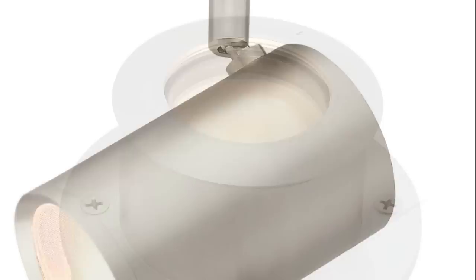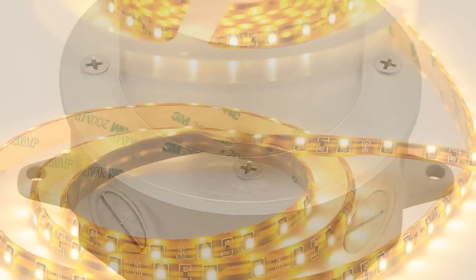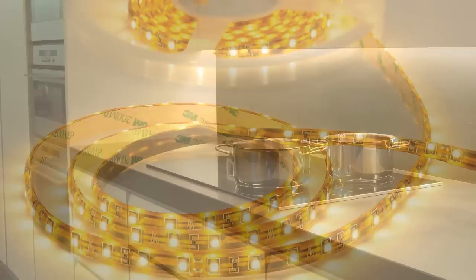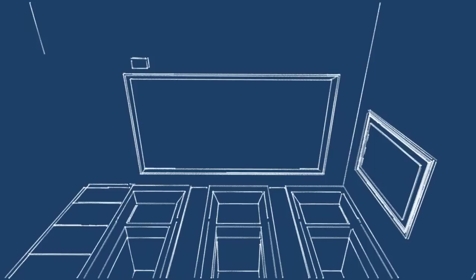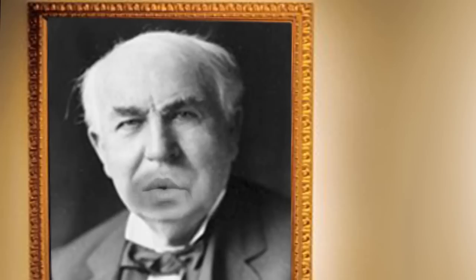Low voltage could mean 12 or 24 volts, whether you're talking about AC or DC. 12 volts makes sense if you're talking about smaller systems, like a soft strip run less than 25 feet, such as under cabinet lighting. But if we have a larger system like cove lighting, we're going to use 24 volts. 24 volts lets us create soft strip runs up to 40 feet with less voltage drop and we can still use the same 14 gauge wire. But what about converting from AC to DC? You can either do that right on board the fixture or you can use a remote power supply, but either way you still have to convert your AC to DC using a rectifier.